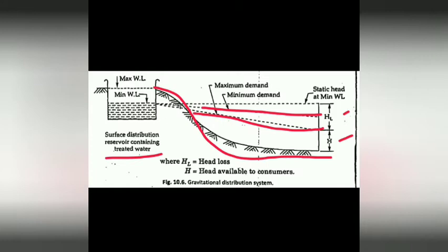In order to achieve this, the gravitational flow should be available, and for proper functioning of this system, the difference of head available between the source and the localities must be sufficient as to maintain adequate pressure at the consumer's doorsteps, after allowing for the frictional and other losses in the pipes. And this method is most economical and reliable since no pumping is involved at any stage, and hence it needs a lake or a reservoir as a source of supply. In Mumbai, the water which is brought from the high lakes situated in the hills is distributed to the consumers by this method.